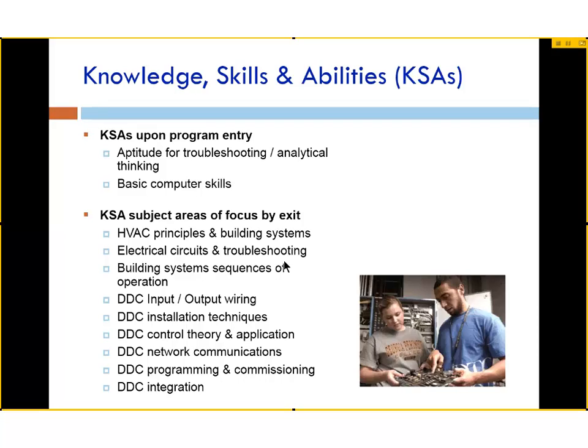Electrical circuits and troubleshooting: graduates of this program have to be very familiar with using an electrical meter, because automation systems basically boil down to a decision-making electronic device which takes specific inputs and generates a control response or output. Fortunately, those inputs are standardized to about 5 or 6 standard physical inputs that students have to be able to wire, check with their meters, and calibrate, plus about 3 to 4 common types of outputs.